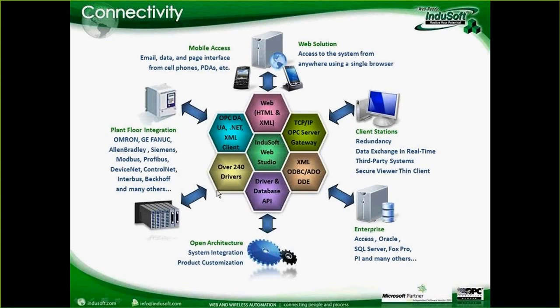If we don't happen to have the driver for the particular device that you want to communicate with, you can optionally use OPC to get to those devices. And we support many different OPC technologies. The OPC that many people are familiar with is OPC DA, which is OPC Data Access, and the OPC Foundation is now calling that OPC Classic. And that has to run on a Windows PC because it uses COM and DCOM for the communication mechanism. That's an older Windows communications technology.